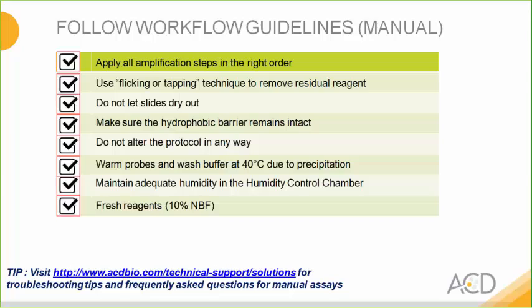And as I mentioned before, use the flicking or tapping technique to remove residual reagent. Do not let the slides dry out. Now, you may notice in the user manual that there are very specific parts of the assay where it does call for drying out or dehydration, for example, when you have to draw the barrier using the ImmEdge pen. So unless otherwise stated in the user manual, please do not let the slides dry out.